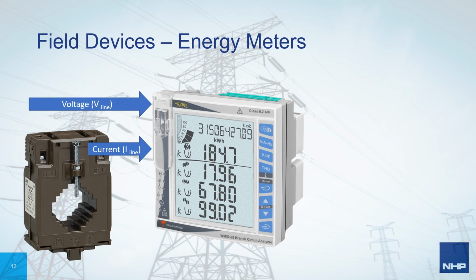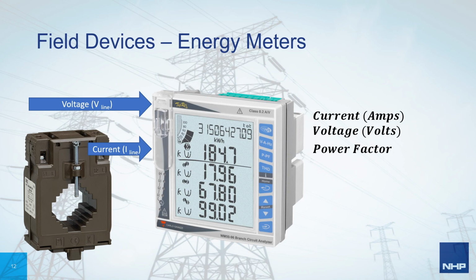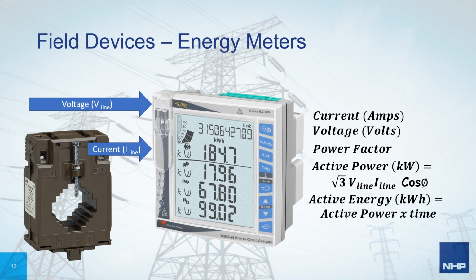The line voltages are also connected to and are measured and displayed by the energy meter. The meter measures the electrical displacement angle between the current and voltage waveforms and displays this as power factor, commonly referred to as cos phi, or the cosine of phi. And from this data, it continually calculates the instantaneous values of apparent power, reactive power, and most importantly, active power. Active power is usually expressed in kilowatts and is calculated as the square root of 3 multiplied by the line voltage, multiplied by the line current, multiplied by a cosine of phi. You can see it displayed individually for the 3 lines in the image. If then we take our active power and multiply it by the passage of time, we have active energy.